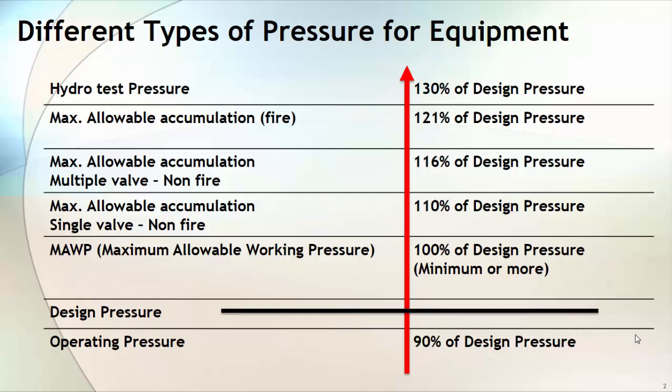Operating pressure is based on your process condition. You add some safety margin on that, which becomes your design pressure. Based on this design pressure, your equipment manufacturer designs the equipment and comes up with a number — usually equal to or more than your design pressure — that becomes your maximum allowable working pressure. Hydrotest pressure is calculated based on the equation given in the construction code. In the case of ASME, hydrotest is normally 1.3 times your design pressure.